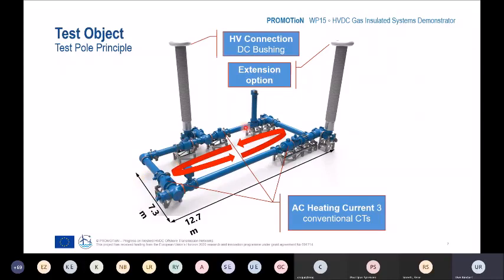Moreover, we have some disconnectors and earthing switches, so in total 3 here. A lot of monitoring and diagnostic devices, so partial discharge measurement, temperature measurement, current and voltage measurement, and also arc detection equipment here.